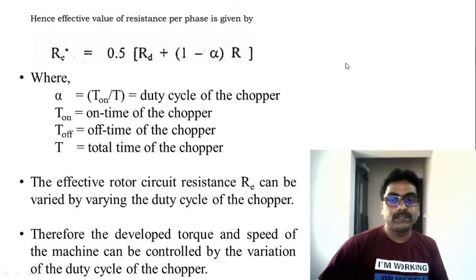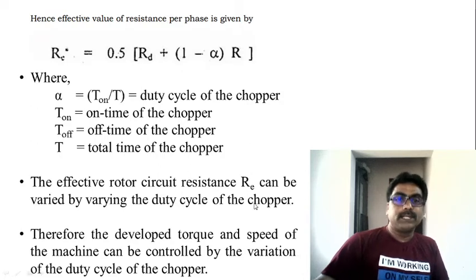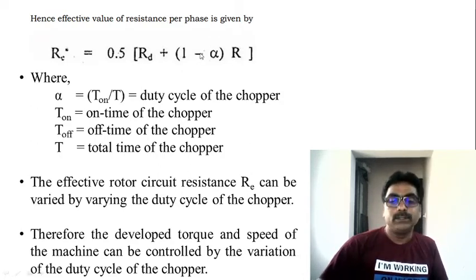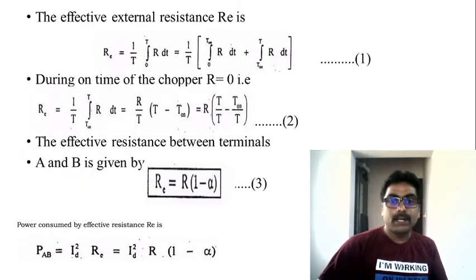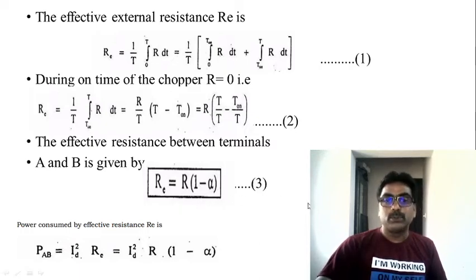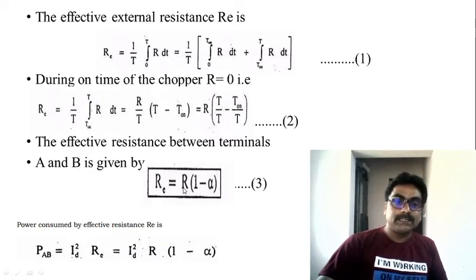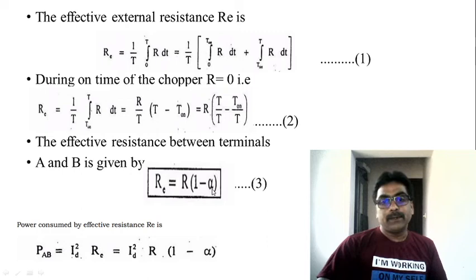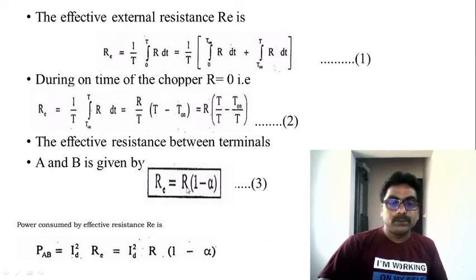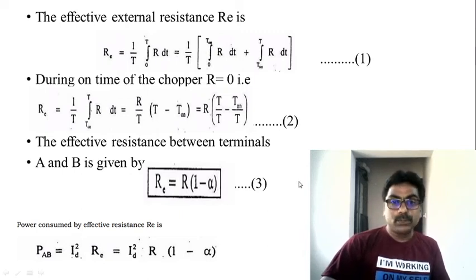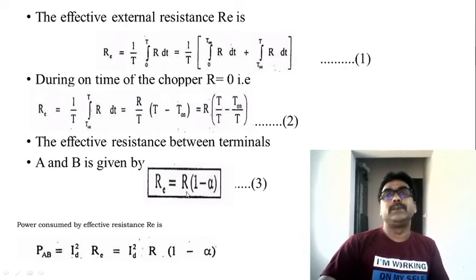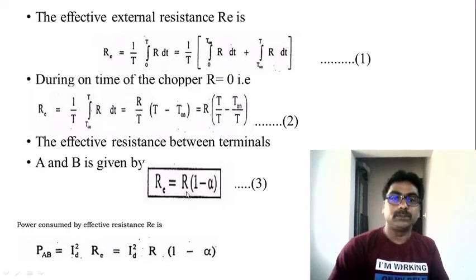The effective rotor resistance R_eff can be varied by varying the duty cycle of the chopper converter. Using the simplified equation R_eff = R × (1 − α): by varying the duty cycle α from 0 to 1, you can effectively vary the resistance from R (maximum, when α = 0) to 0 (when α = 1). So by varying α from 0 to 1, the effective resistance varies from R to 0.